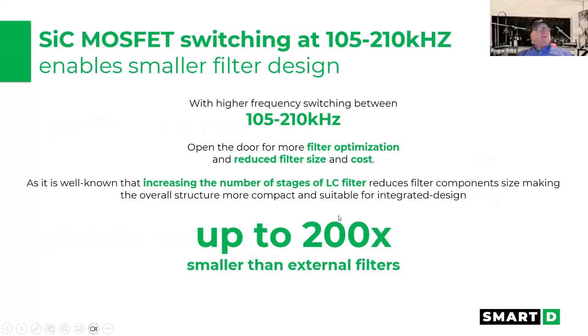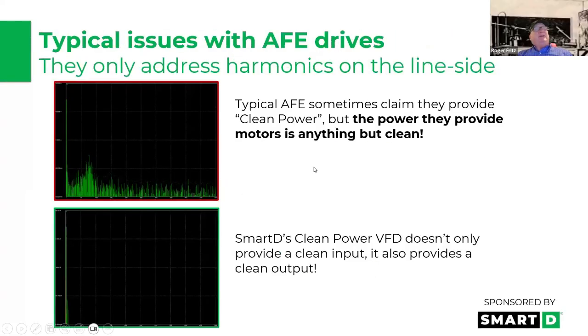And then because it's in the high frequency range, we're using much better LC filters to reduce any noise that is created. So our output becomes very clean on the output side. Plus we have the active front end on the front side. So you can see we have very, very minimal noise compared to all of this noise that's created. And the only way you can see that is with a Dranetz meter or a Fluke meter, and most of the time these are in the price range of $6,000 to $7,000. A standard amp meter is only based around your 60 hertz part, so they never see those currents that are going out to the motor. But all that energy's got to go somewhere.